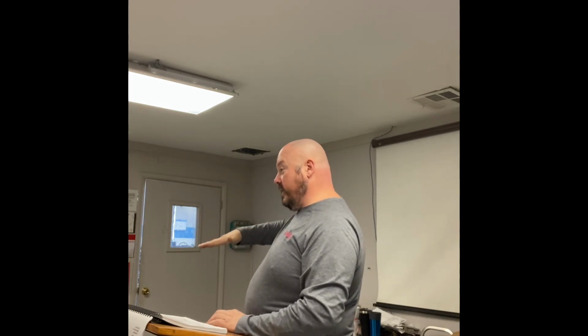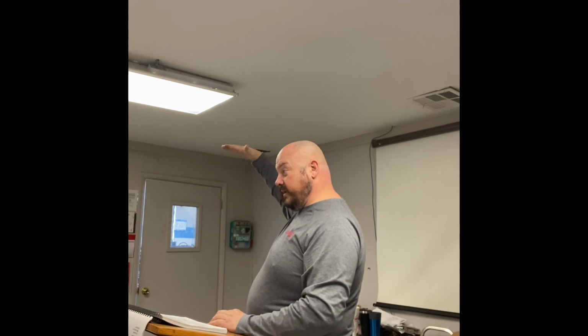We haven't talked about this that much. We talked about it a little yesterday. SEER rating. SEER. Seasonal Energy Efficiency Rating. Government. More government. Okay? Remember we talked about how you have to have 14 SEER or higher. In Arkansas and Missouri, you're still allowed 13 SEER. Okay? So if I replace her coil on her system, I have opened her system up, I have replaced a portion of it, put it back together, and made it work. Does it perform to 14 SEER at this point? You don't know? Probably not. Even if it's an awesome coil.